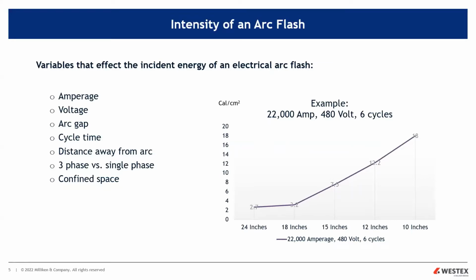Voltage is not as critical, just need to have enough voltage to sustain an arc. Of course, another critical thing is the cycle time or the clearing time. The shorter the cycle time or the shorter the clearing time reduces the incident energy. And of course, that's why companies invest in overcurrent devices to keep that cycle time short to lower the incident energies, engineering controls, if you will.